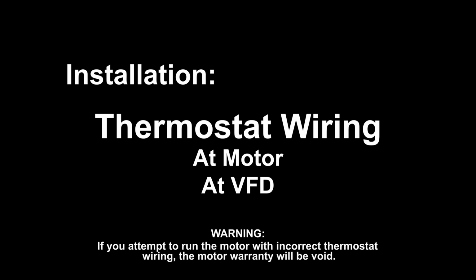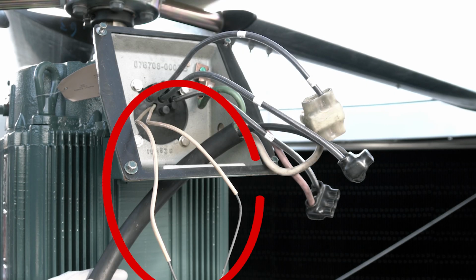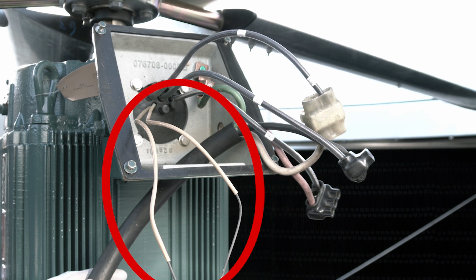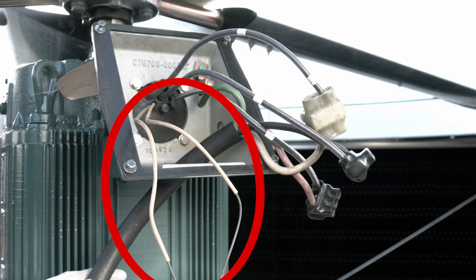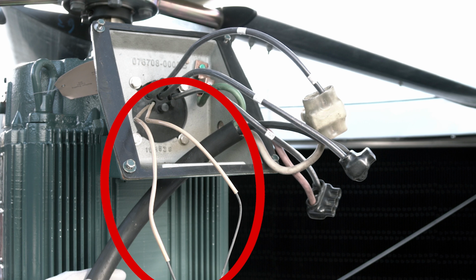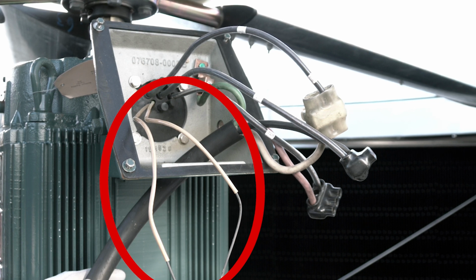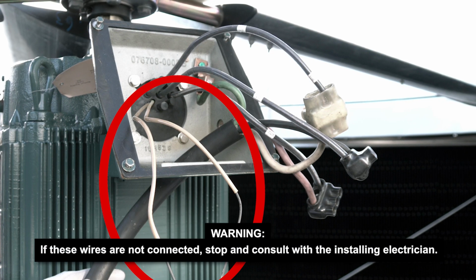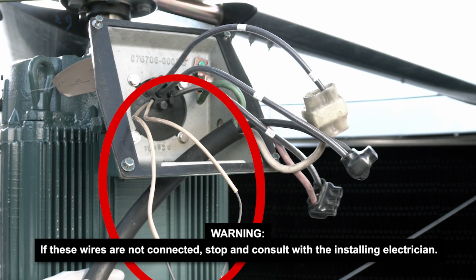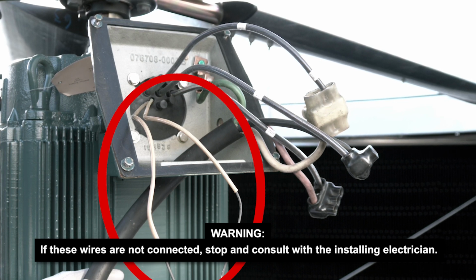Thermostat wiring at the motor and at the VFD. Let's start by ensuring the motor thermostat is correctly wired. This is important. If you attempt to run the motor with incorrect thermostat wiring, the motor warranty will be void. Ensure the motor thermostat wires are correctly installed. The thermostat wires are the two small identical wires coming from the motor. They should be connected to field wiring running inside its own separate conduit. If these wires are not connected, stop and consult with the installing electrician.